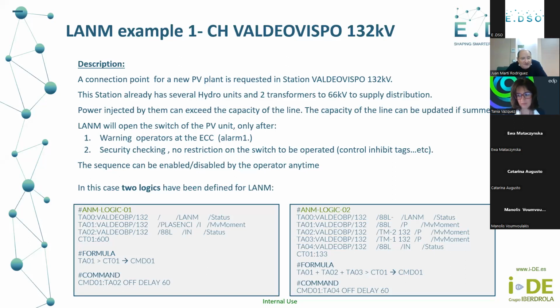In the logic on the left, we simply supervise the current in the transmission line and define which breaker is going to open. The constant is 600, because 600 amps is the trip level, and then we define the command, which can include a delay, so we wait out the overload for a period, like a typical overload protection.